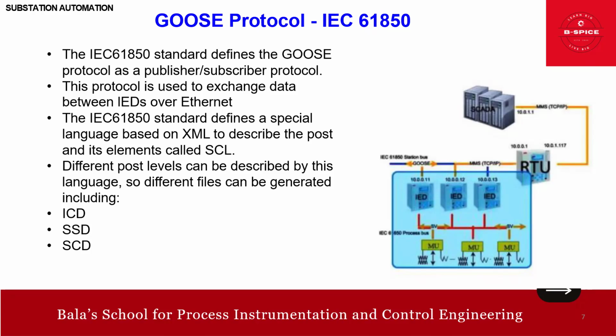Okay, so data sets. Then communication mapping. SCL maps the logical nodes and data attributes to the physical communication network. This mapping is essential for the correct routing and delivery of GOOSE messages. I'm going to talk about that in the next slide with the diagram, so you'll understand the mapping even better. Then interoperability: by using SCL, engineers can ensure that GOOSE messages are correctly interpreted by all devices in the substation, regardless of the manufacturer. And of course, the engineering process also. SCL simplifies the engineering process by providing a clear and consistent way to configure and document the substation communication and control system.